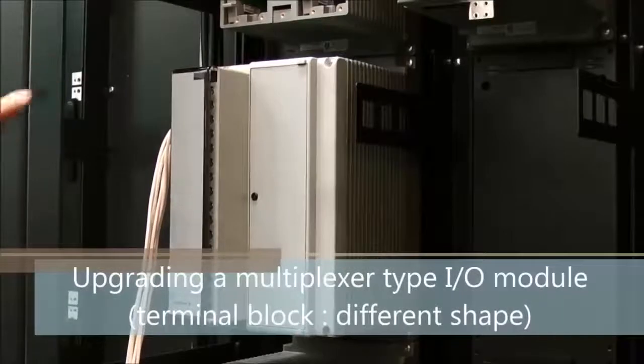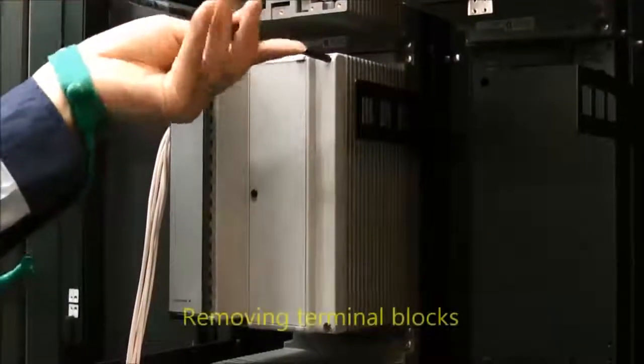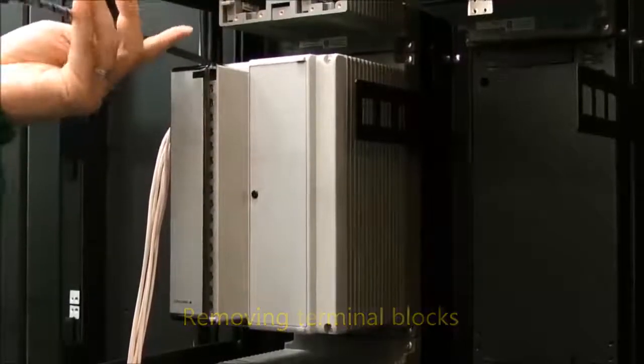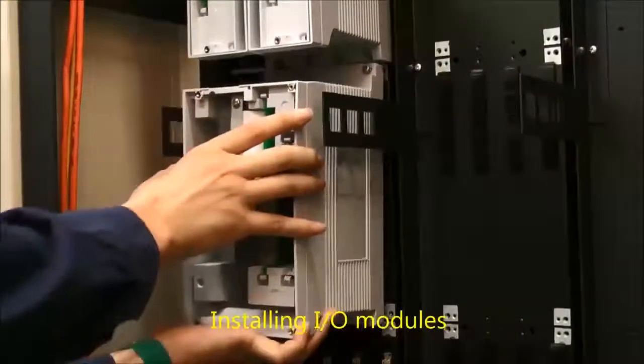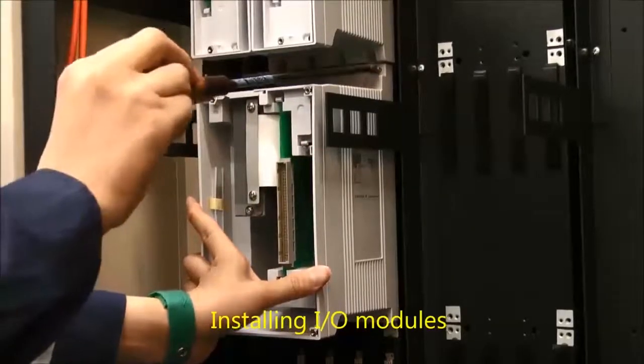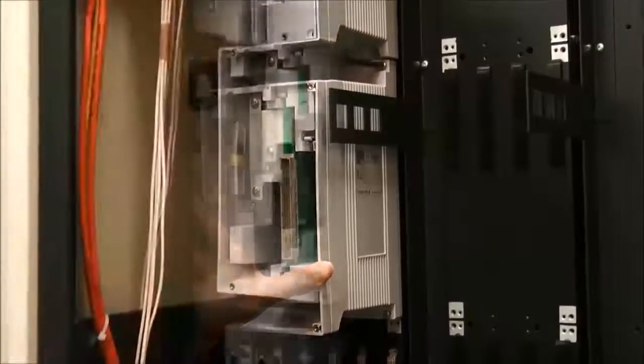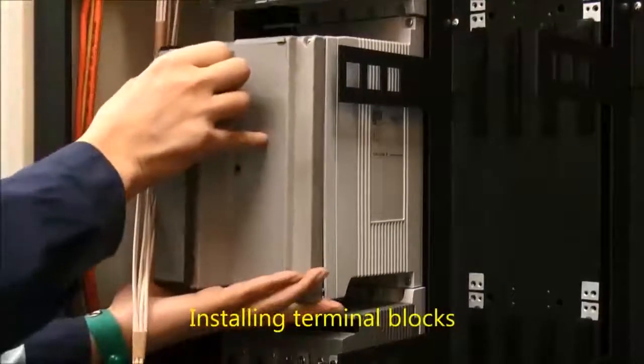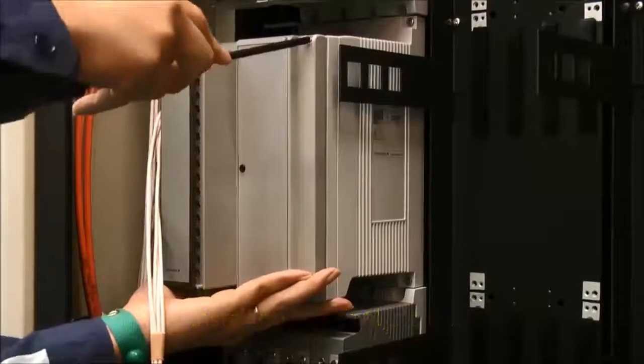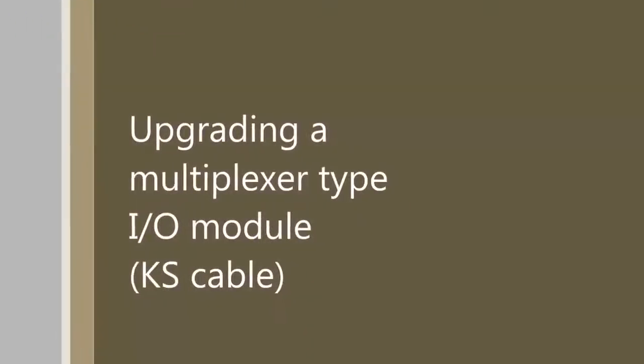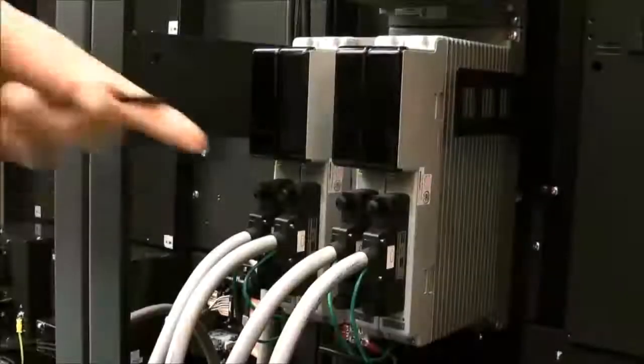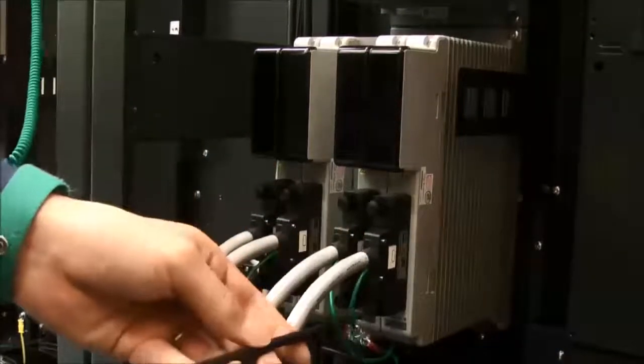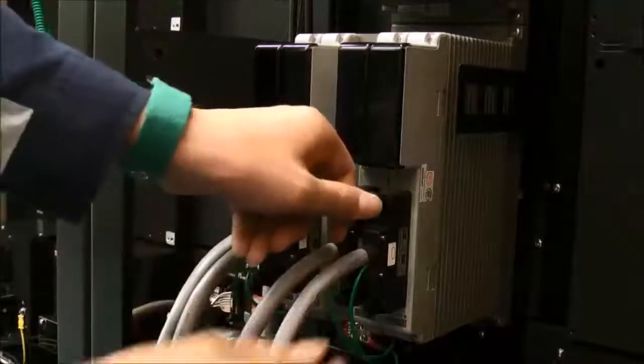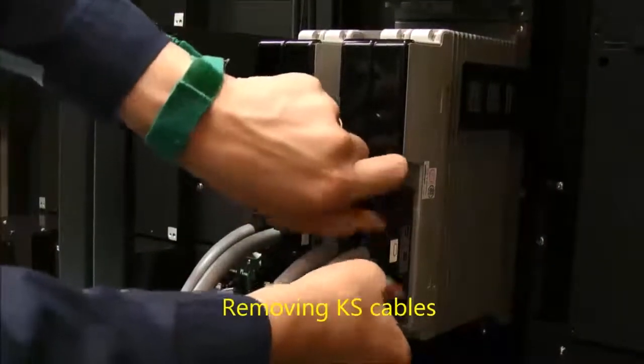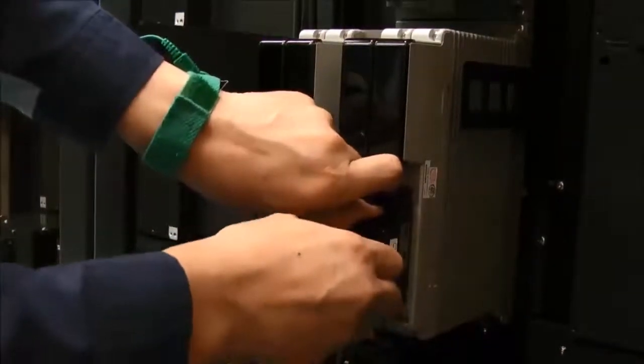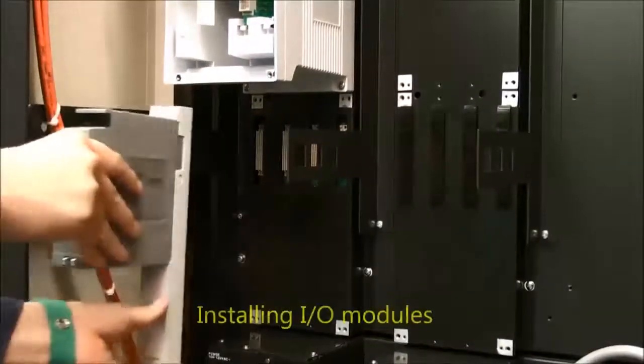The terminal block may have a different shape, like this example. However, you can replace with a new I/O module through the same procedure. A multiplexer module with connector cables attached to it can be replaced by separating the signal cables from the I/O module and connecting them to a new module. After removing the ground wire, remove the signal cables from the existing module. Mount a new I/O module on the node and connect the ground wire and signal wires back in.